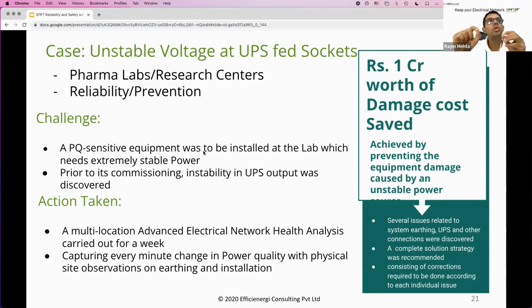They simply found neutral to earth voltage beyond 1 to 2 volts - that's what all these OEMs will harp on. So we went ahead and did a detailed multi-location advanced electrical network health study for a week, deploying multiple analyzers and capturing hundreds of parameters while also looking at site-related observations. We found several issues related to system earthing, the UPS, other cross connections, and unbalancing in the load.